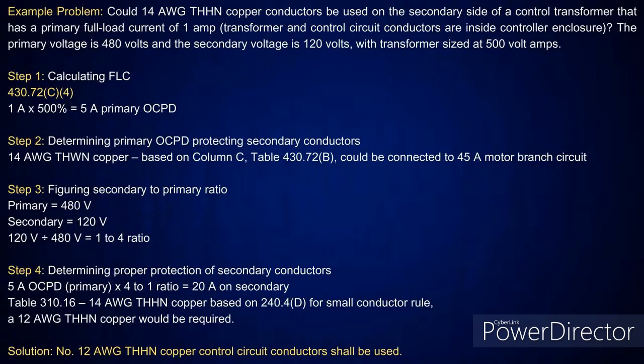All right, so step 3, I'm going to take the 480 volt primary and divide it into the 120 volt secondary. That's going to give me a 4-to-1 ratio. So when I'm determining the proper protection of those secondary conductors, I've got a 5 amp primary times a 4-to-1 ratio, and that's going to give me 20 amps on the secondary. So if I go over and look at Table 310.16 and tie it in with 240.4(D) for my small conductor rule, it's going to tell me that number 12 copper conductors would be required instead of the number 14.